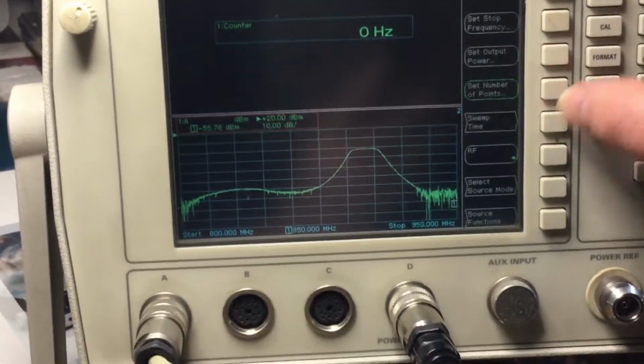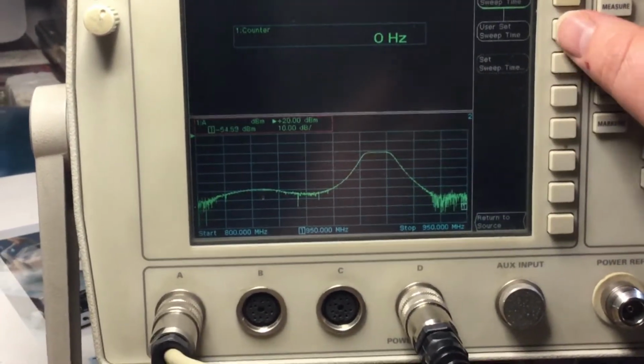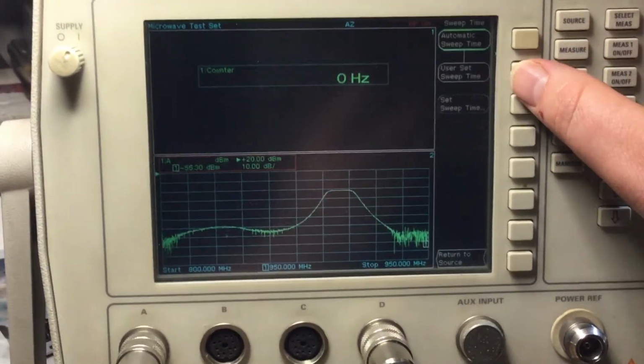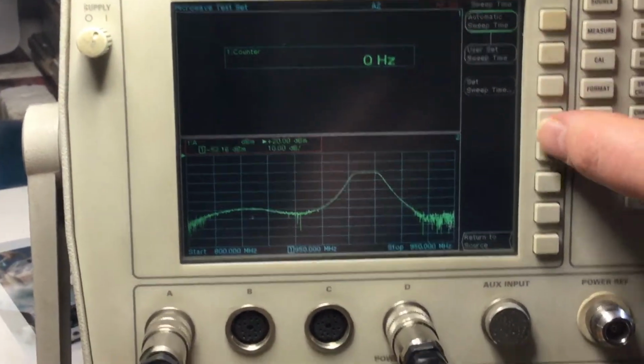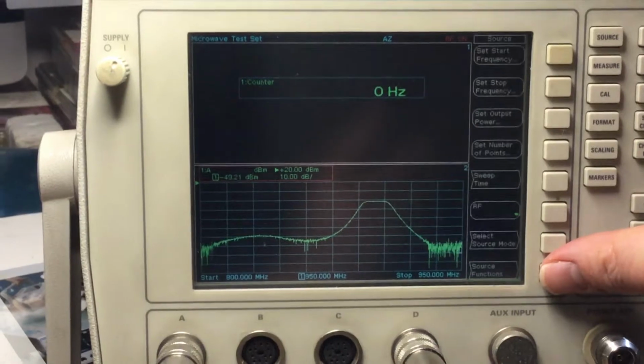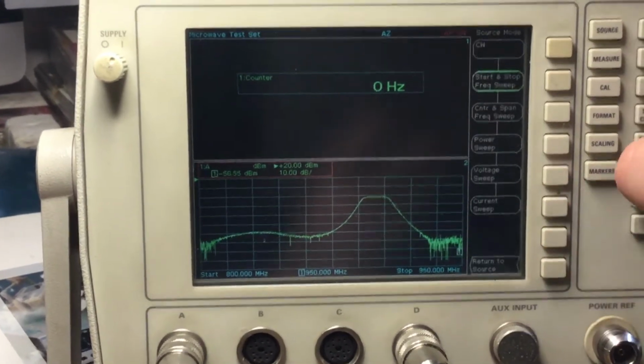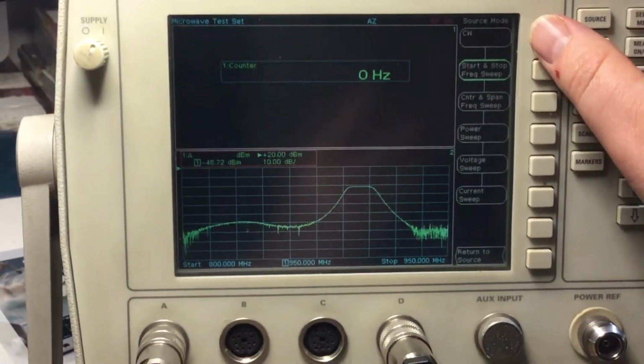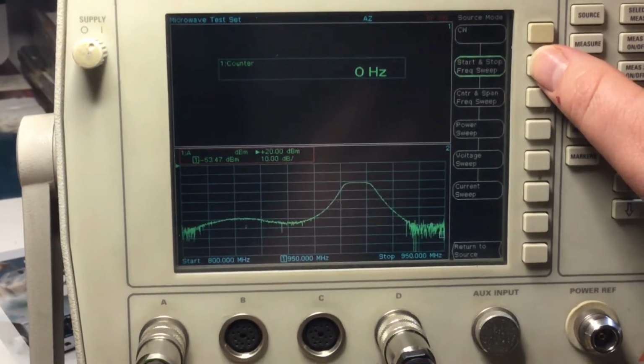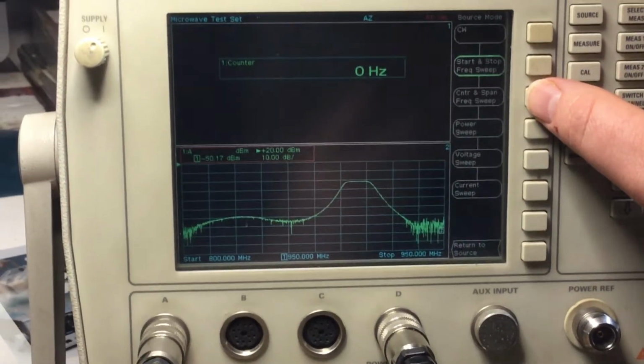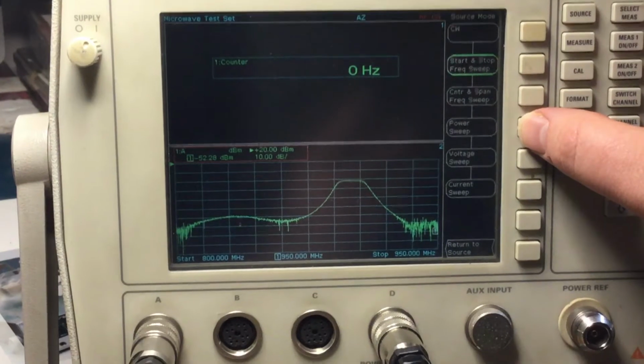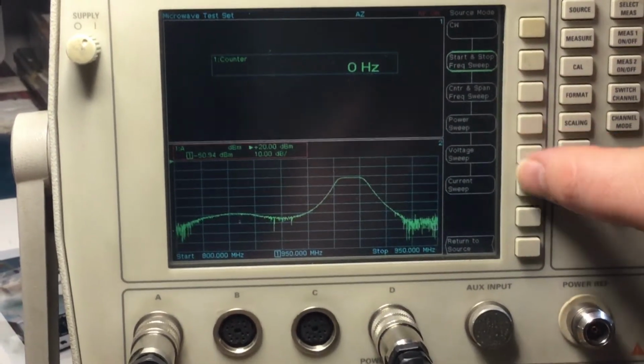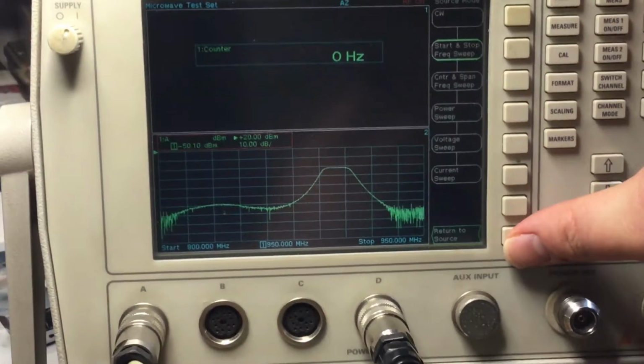We've also got the sweep time, which we can adjust - either set to automatic or manually set user settables. We've got a source mode, so we can have it as CW, start and stop frequency, center and span, and frequency sweep, power sweep, voltage sweep and current sweep modes.